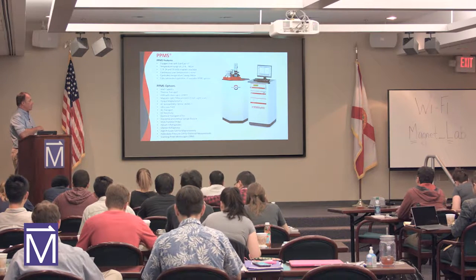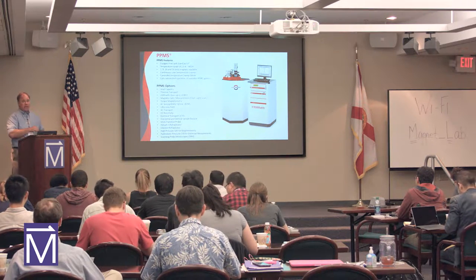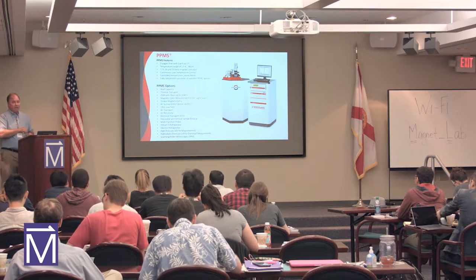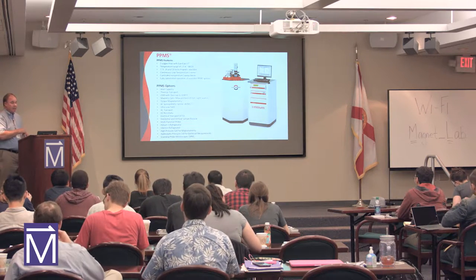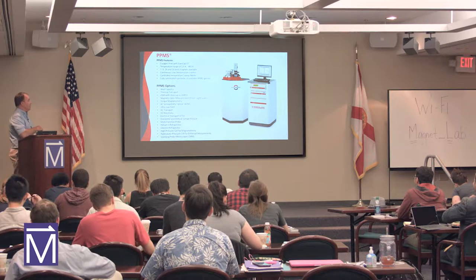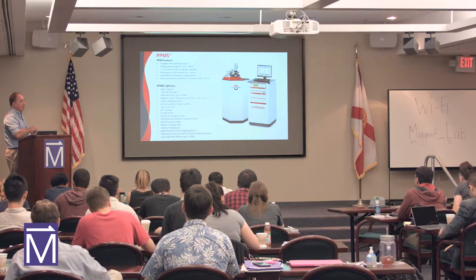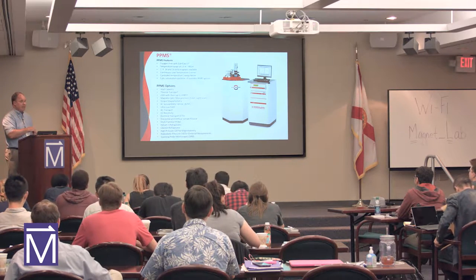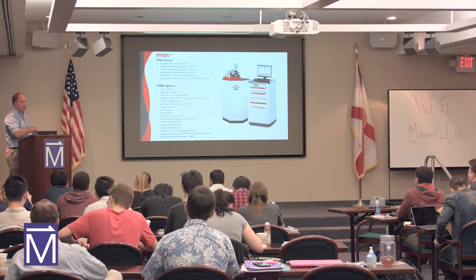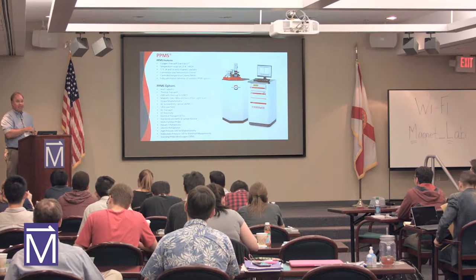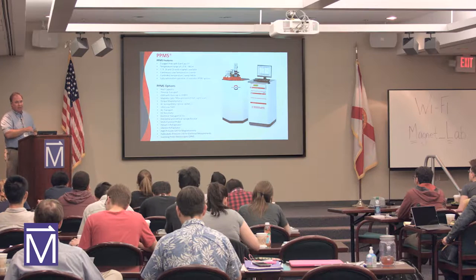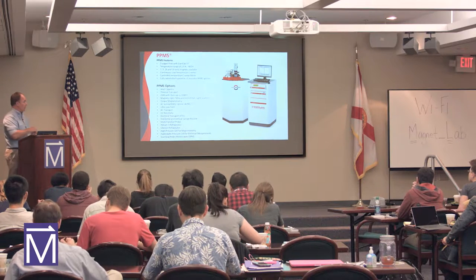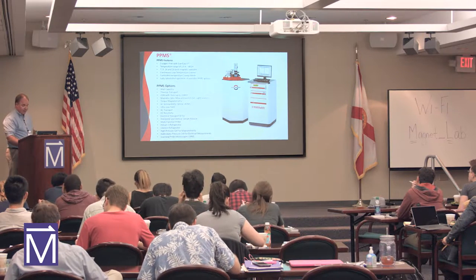So this is the Evercool version. So this is the cryogen-free version of the system. We have the 16 Tesla wet liquid helium system, and 7, 9, 14, and 16 Tesla PPMS units. We still sell wet systems. They're probably not as many, but a place like the Magnet Lab, you have a lot of helium, so you can accommodate that number of experiments.